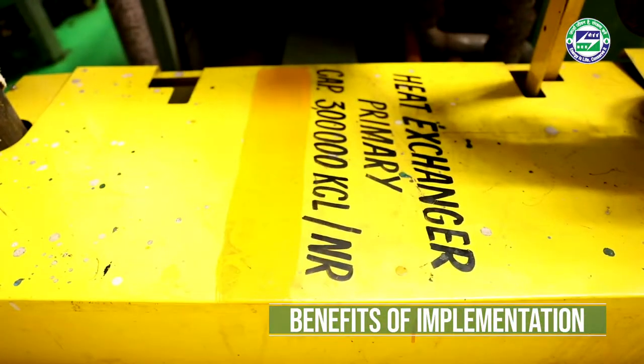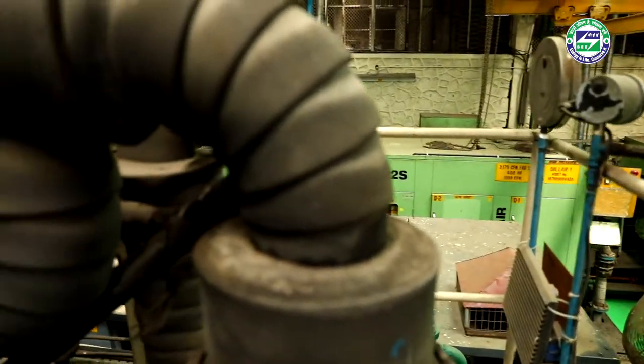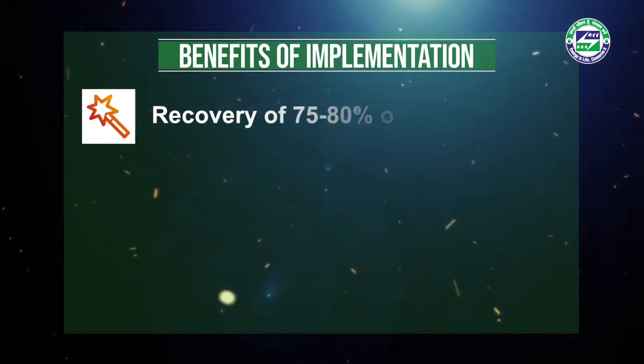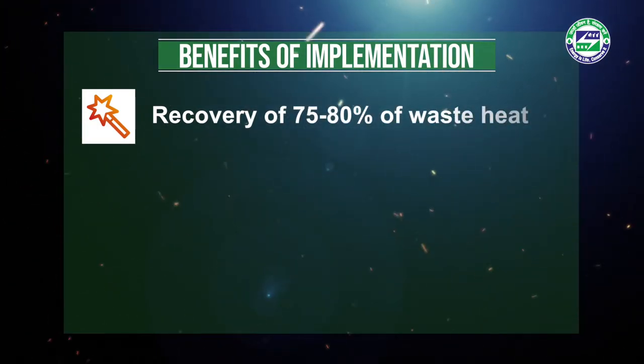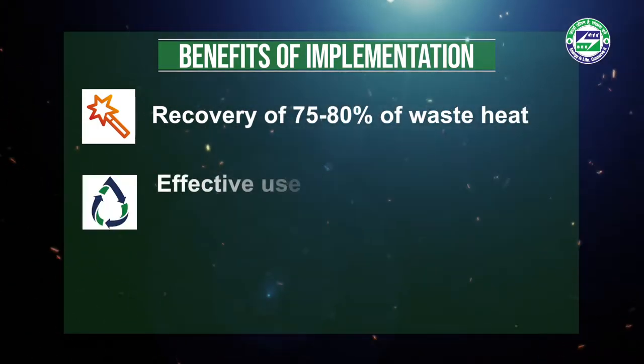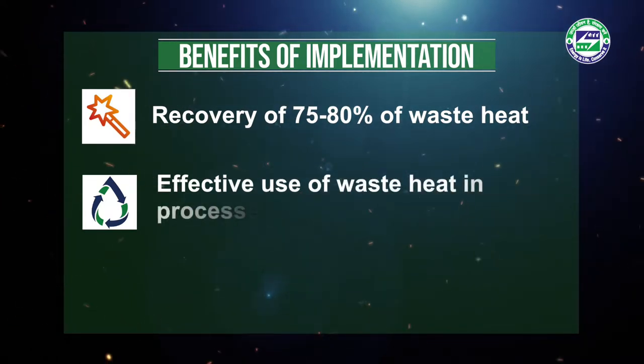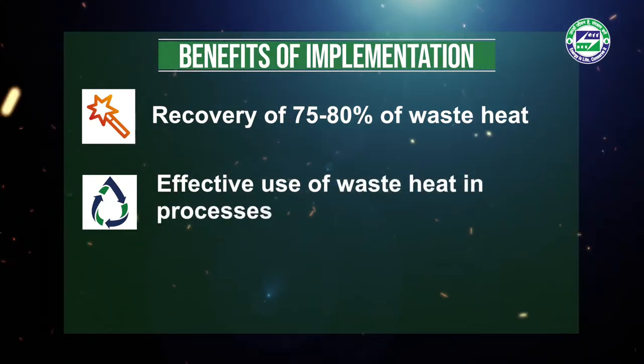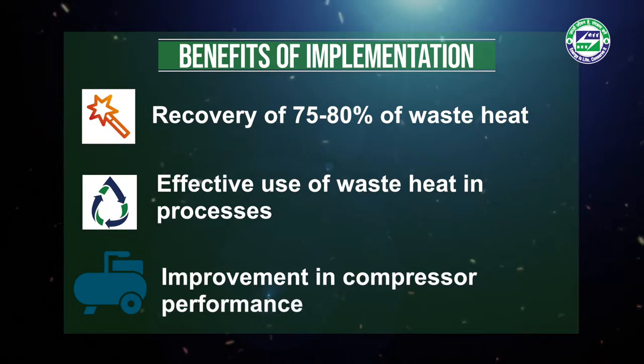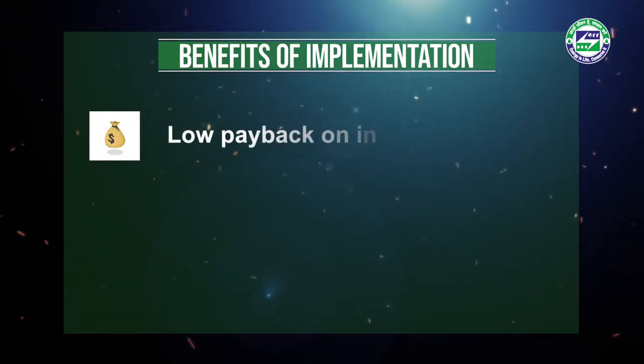Main benefits: installation of a waste heat recovery unit in compressors leads to 75 to 80% of the waste heat energy being recovered. Waste energy recovered can be directly used in the process or utility. It enhances performance of the compressor and gives a low payback on investment.